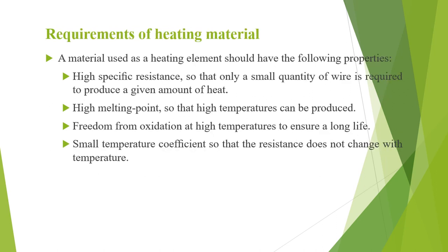Requirements of heating material: a material used as a heating element should have high specific resistance so that only a small quantity of wire is required to produce a given amount of heat; high melting point so that high temperatures can be produced without jeopardizing the life of the heating element; freedom from oxidation at high temperatures so that long life is ensured; and small temperature coefficient so that the resistance does not change with temperature increase. Materials that most satisfactorily fulfill these requirements are alloys of nickel and chromium containing about 80% nickel, or alloys of 65% nickel, 15% chromium and 20% iron.